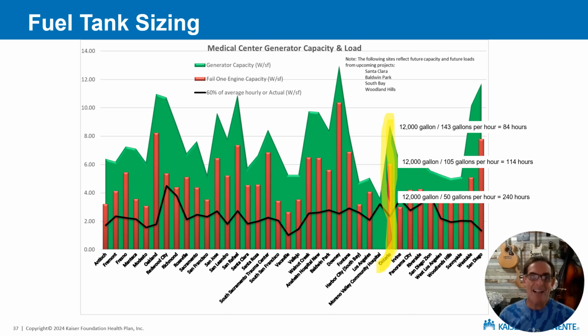The load that we actually would put on the generator, the black line down there, is about a third of the nameplate capacity, which means that with that 12,000 gallon tank, if we were to run those generators, we would actually get about 240 hours out of them, which is 10 days.